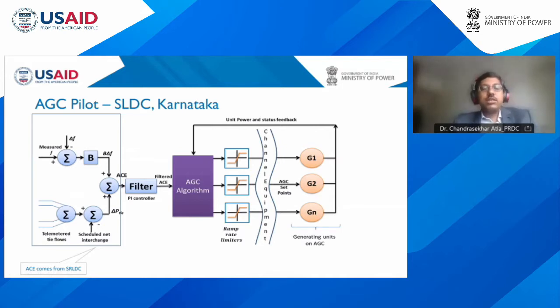When it comes to the SLDC, this is mostly applicable to all state load dispatch centers in India. As you know, the area control error generally comes from the regional load dispatch centers. In this case, SRLDC, the Southern Region Load Dispatch Center, provides the area control error for each state. As we already get the area control error from the SRLDC, we have bypassed the left side, like frequency or tie-line schedules, which are calculated under the AGC module. That has been bypassed and the signal is taken directly from the SRLDC.